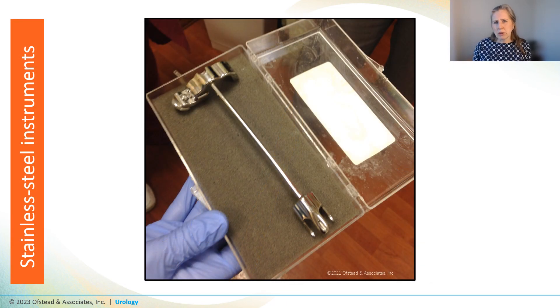When we asked about the needle gouge, they were surprised because they said they use a needle guide to prevent such gouges and showed it to us. It was kept on a piece of foam in a dirty little container, and they said they dunked it in HLD and rinsed it off in the sink in the patient room. This was supposed to be a sterile needle guide for doing biopsies.